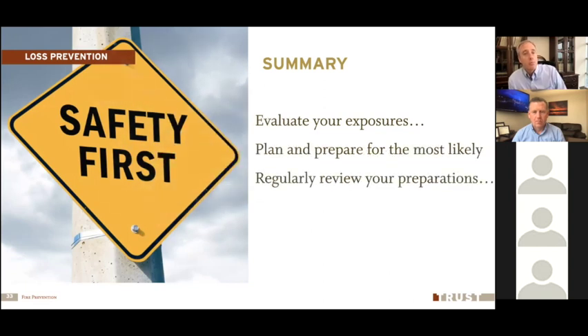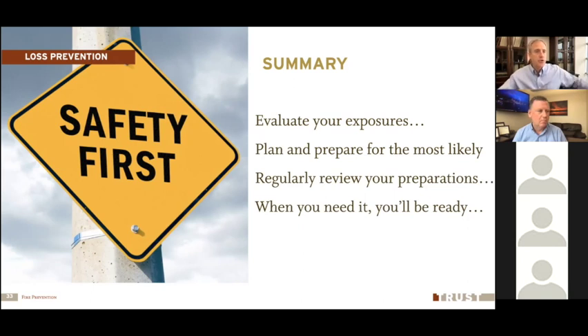And then regularly review those preparations. Just going out and inspecting it one time doesn't do it, because conditions change. The condition of the cords changes, the condition of your equipment, your property, the combustible materials, that all changes. And keep those spaces clear around your building. Keep combustible material back, and make sure dumpsters are moved away from the building. Make sure combustible material like dumpsters or piles of pallets is not right next to or underneath power lines either.